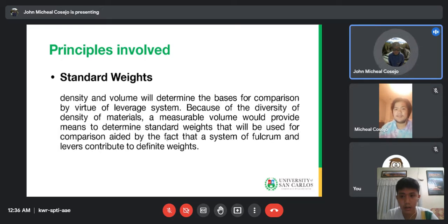Next is the standard weight. In metrological terminology, a distinction is made between reference weight or mass standard and certified weight. The conventional weight value is used as a nominal value of a weight for a higher level of accuracy. Certified weights are calibrated and traceable back to the primary standard, which are usually national standards maintained by National Metrology Institute. The weights used are stainless steel weights because of their long-term stability.